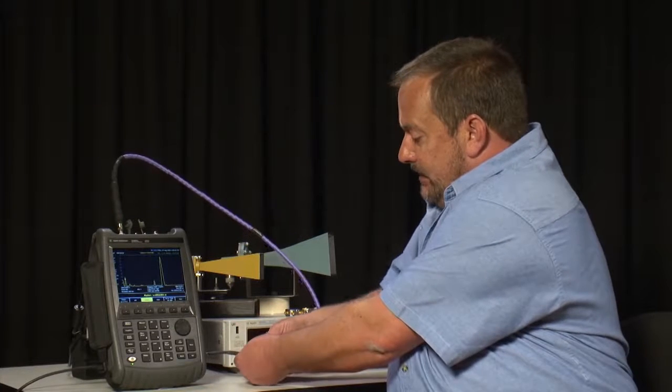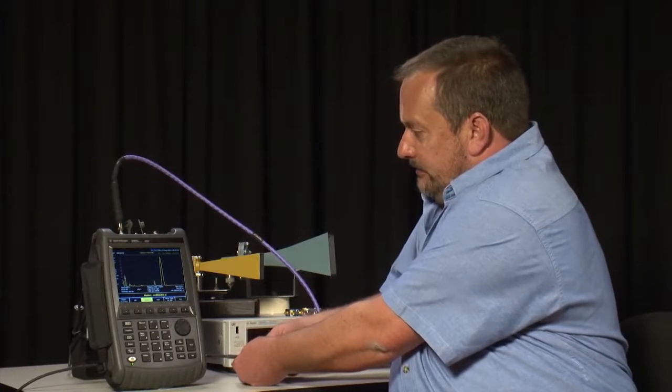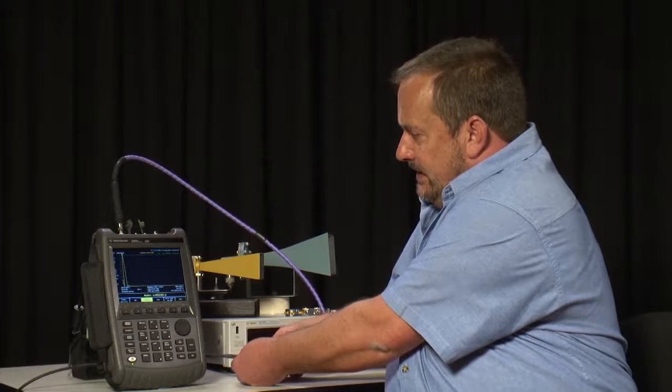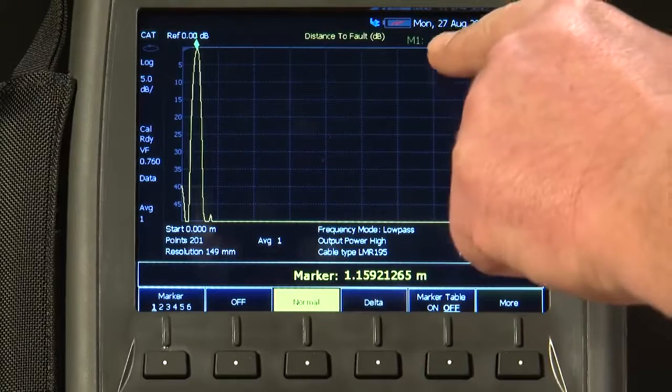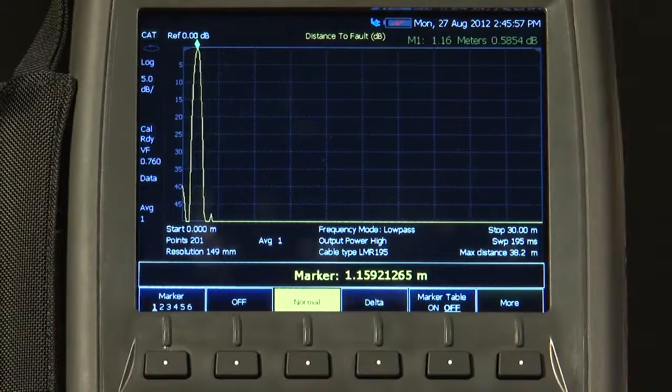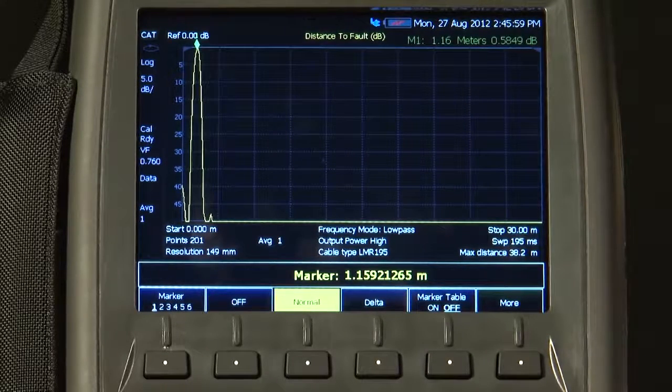I can prove that by disconnecting it for a moment. And you will see now we have got a 100% reflection at that distance, one meter. I will reconnect it.